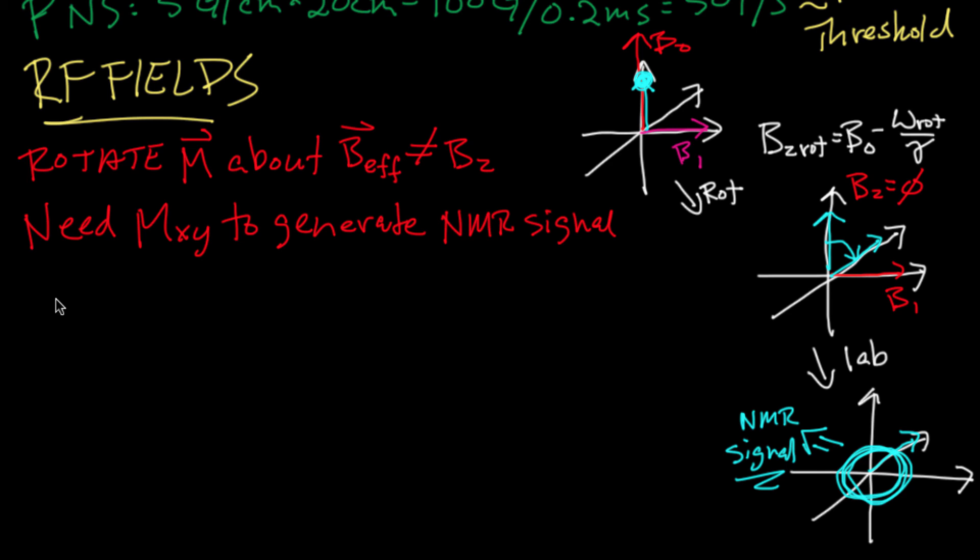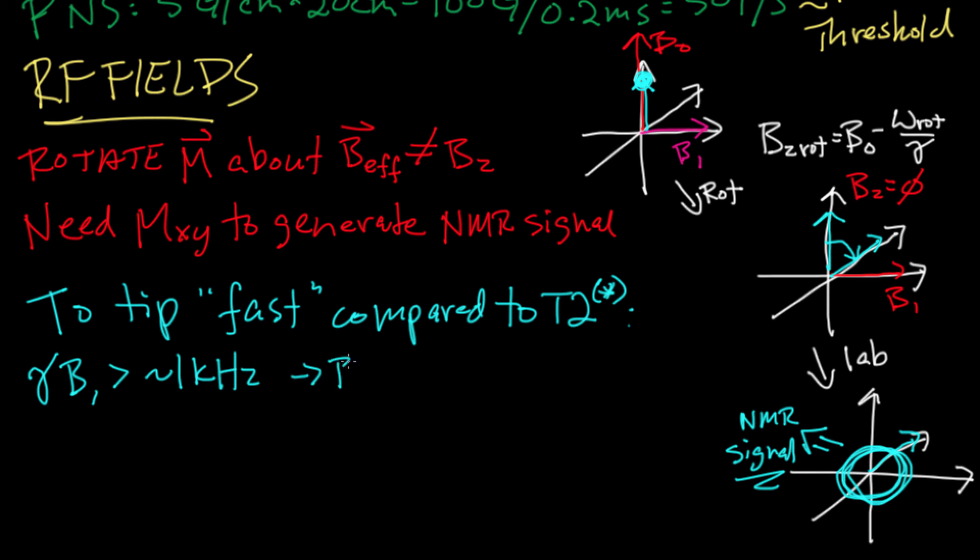So to calculate how big you want the B1 fields to be, the main requirement is that you want to tip magnetization rapidly compared to relaxation processes like T2 and T2 star, which again can be as fast as about a millisecond. So you want the rotation frequency, which is gamma B1, to be about a kilohertz in order to tip things in the millisecond range. And that means that the B1 itself needs to be on the order of 0.1 Gauss. The calculation of the power that's required to generate a particular B1 field is much more complicated than it was for both the main field and the gradient fields. And that's because the power is dominated not by the interaction between the B1 field and spins, but instead the interaction with the B1 field and the lossy structures of the body.